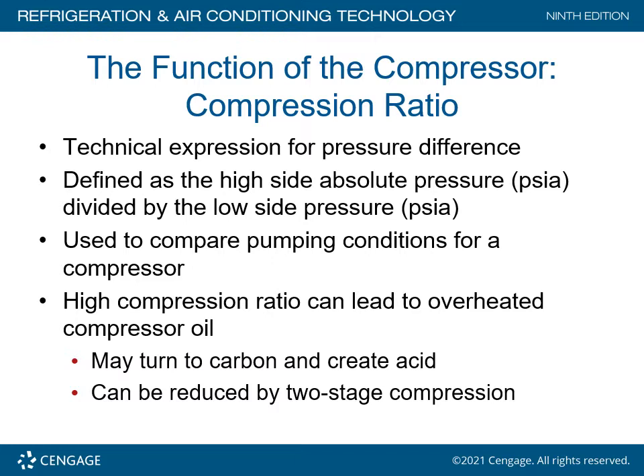Compression ratio is used to compare the pumping conditions for a compressor. A high compression ratio can lead to an overheated compressor oil, which causes loss of lubrication and other problems — it may turn into carbon and create acid. This can be reduced by two-stage compression, and is typically more of a problem in low-temperature or cryogenic refrigeration systems.